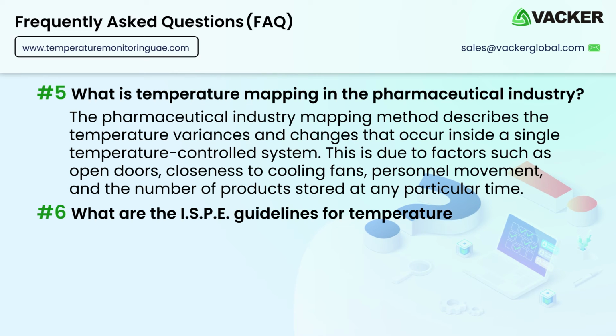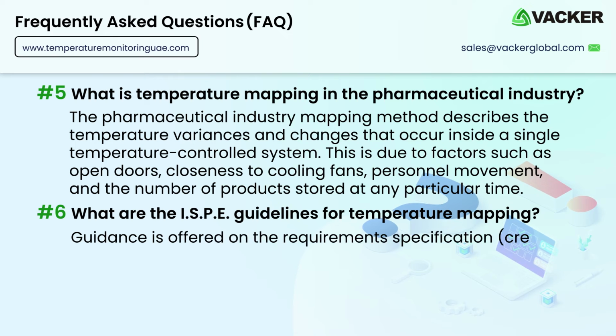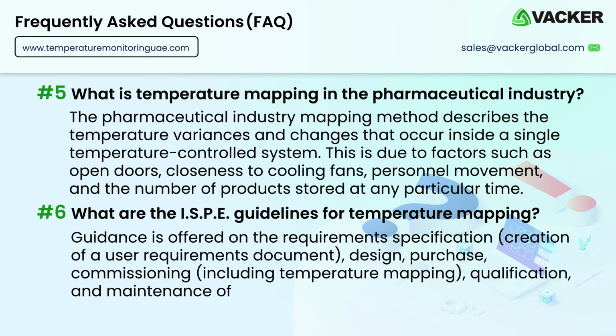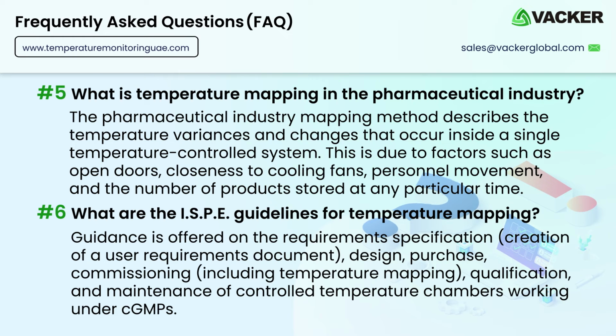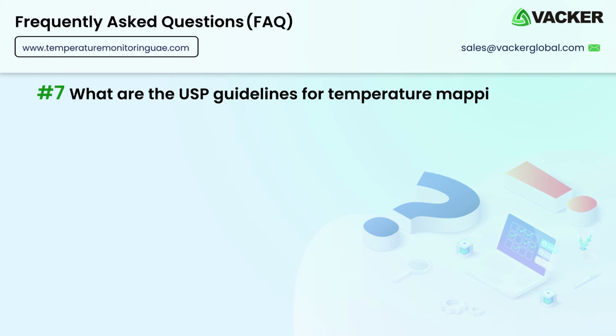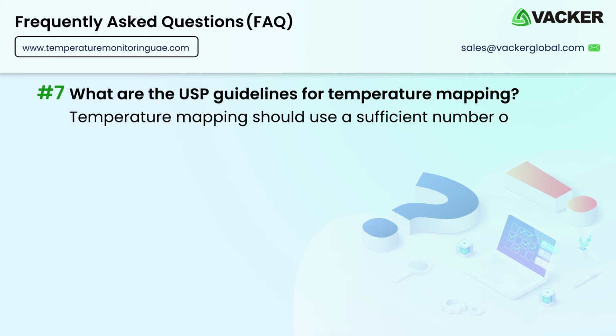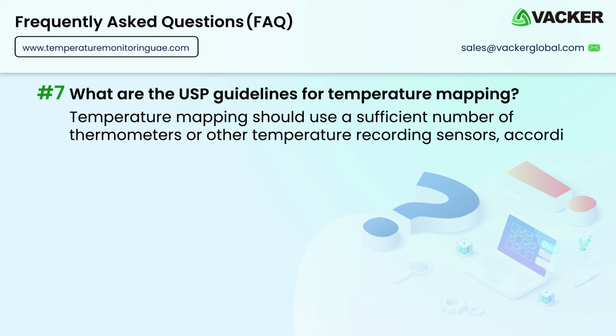What are the ISPE guidelines for temperature mapping? Guidance is offered on the requirements specification, creation of a user requirements document, design, purchase, commissioning, including temperature mapping, qualification, and maintenance of controlled temperature chambers working under CGMPs. What are the USP guidelines for temperature mapping? Temperature mapping should use a sufficient number of thermometers or other temperature recording sensors, according to USP.